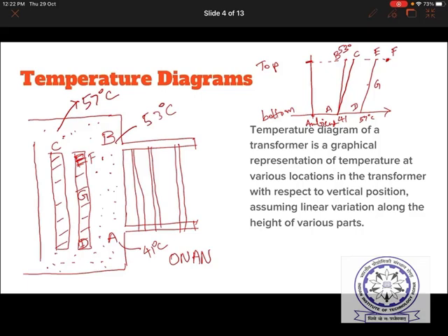For D and E, this is actually the winding, where in both the primary winding and the secondary winding the heat is generated. Wherever heat is generated, there the highest temperatures are expected. From D to E, it is actually parallel to A to C, assuming linear variation, of course. In practice, it is non-linear variation. So, A to C temperature variation you can see here, and A to C is almost parallel to D to E, but D to E is at a higher temperature, 16 degrees centigrade higher. G is the average temperature, roughly around 65 degrees centigrade.